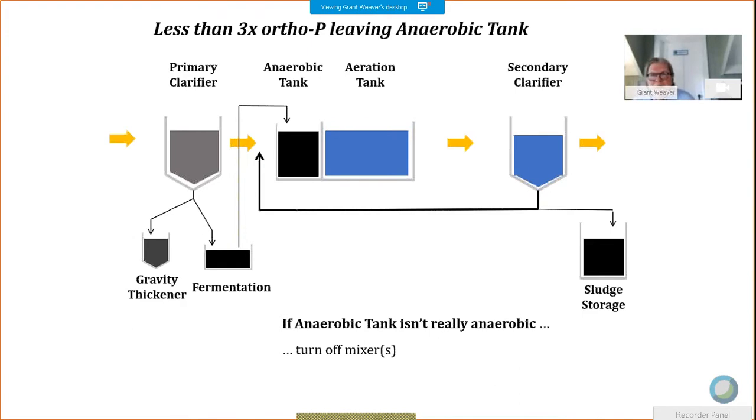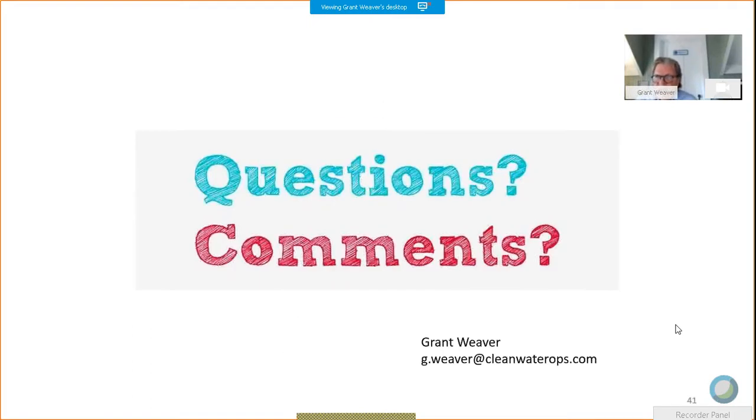Now, it's possible that you get both, that aeration tank's doing its job, yet the effluent still has a higher phosphorus than what you need it to be. And that can happen by getting a secondary release. So the phosphorus is removed, it goes in with the sludge, and then something happens. There's a channel leading to the clarifier that's silting in, and if it does, the bacteria are dying and releasing phosphorus. Don't want any of that. You have to keep no sedimentation from the aeration tank all the way out to the outfall. The more likely possibility is your sludge blankets are getting released in your waste sludge. So the fix on that is to increase your sludge wasting or sludge return rate and lower that sludge blanket. Okay, enough of that. Any questions or comments on that?